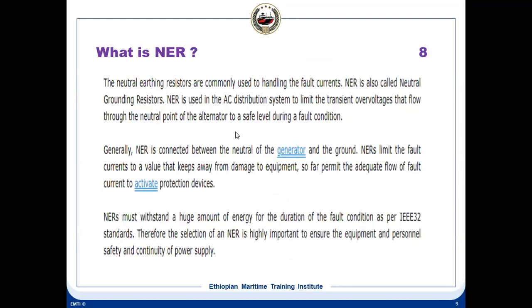Now the NER, there are some specifications. What is NER? It is called neutral earthing resistor, which is used to handle the fault current. Basically, it is to limit the current which is flowing because of this earth fault. NER is also called neutral grounding resistor. It is used to limit the transient voltage that flows through the neutral point of the alternator to a safe level during fault conditions.